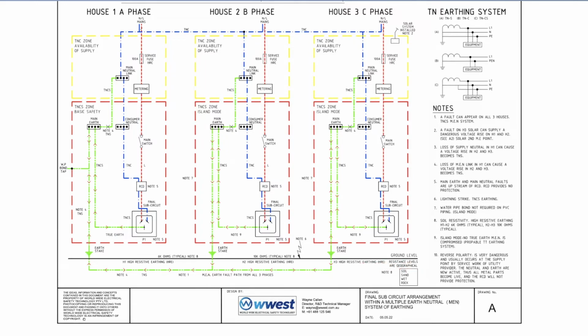So then we go down to our last note, which is island mode. There's no true earth, and MEN relies on a true earth connection. And the M is the multiple. They want multiple true earth connections. And this is compromised. And so when you go into this island mode, it's probably a TT earthing system. So if you go back up here, it's none of these 3. You look at your TN earthing system down here.